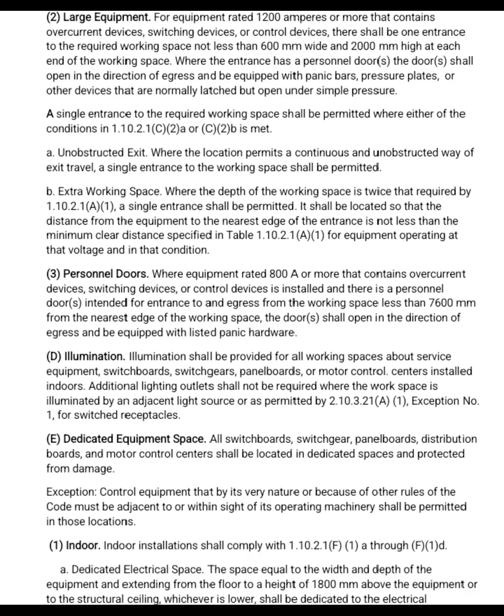Number 2. Large equipment. For equipment rated 1200 amperes or more that contains overcurrent devices, switching devices, or control devices, there shall be one entrance to the required working space not less than 600 mm wide and 2000 mm high at each end of the working space. Where the entrance has personnel doors, the door shall open in the direction of egress and be equipped with panic bars, pressure plates, or other devices that are normally latched but open under simple pressure.